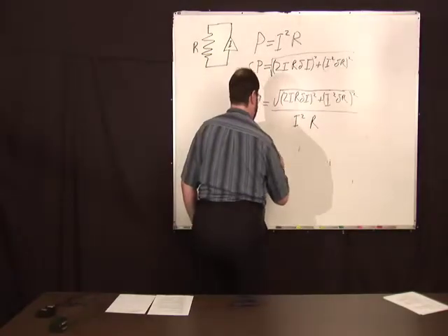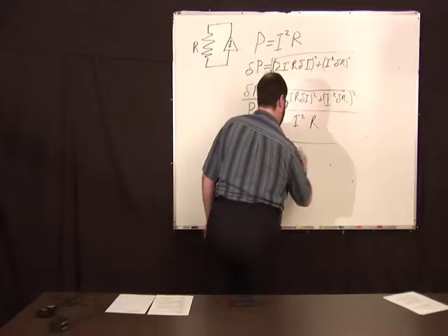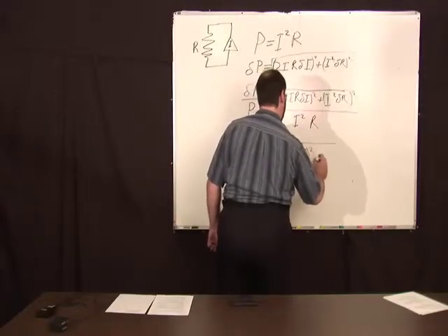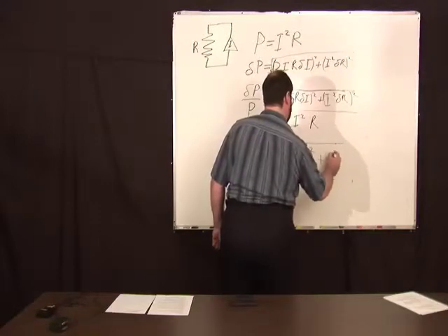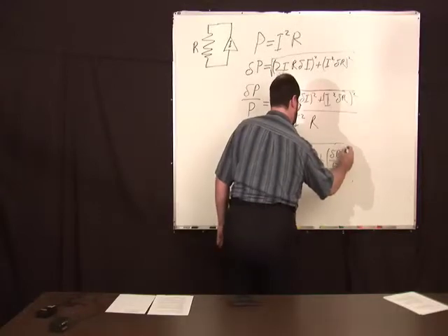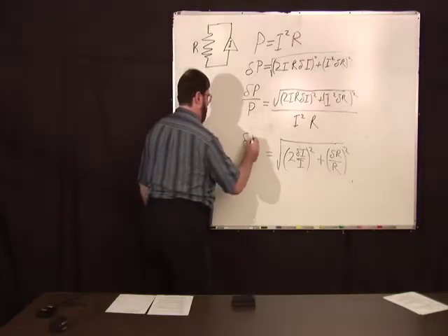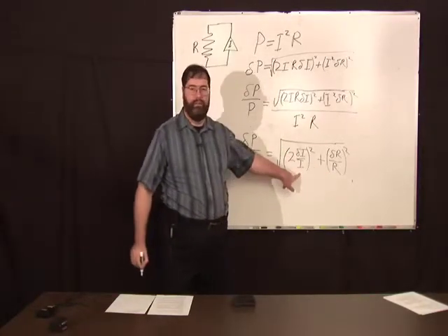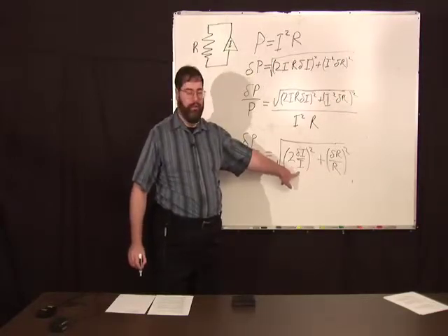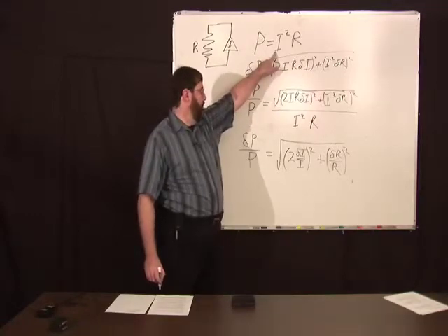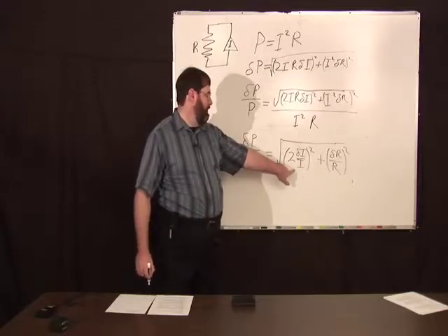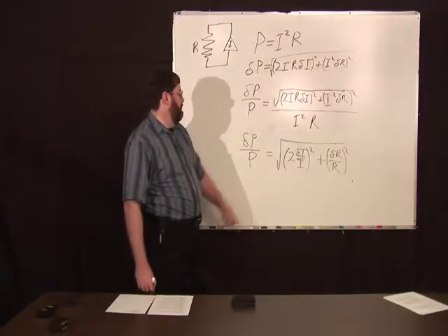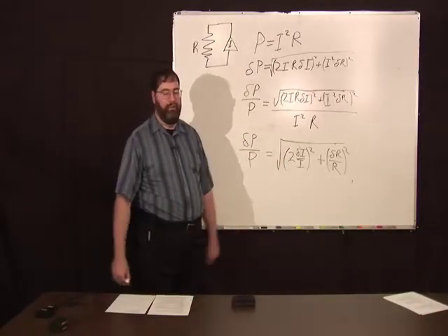With just a little algebra, that becomes... Now in this case, the relative uncertainty of the power measurement, you get the RSS of the relative component of the resistance plus twice the relative component of the current. In this particular case, because of the nature of this measurement equation, a relative uncertainty in the power has twice the contribution from the relative error of the current than the resistance. Now these coefficients up the front, for that reason, are called sensitivity coefficients.